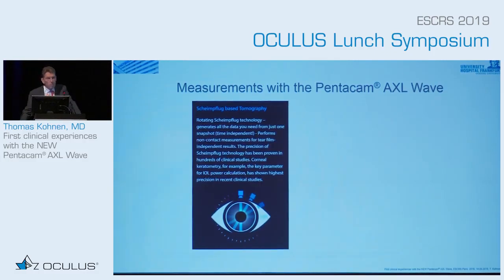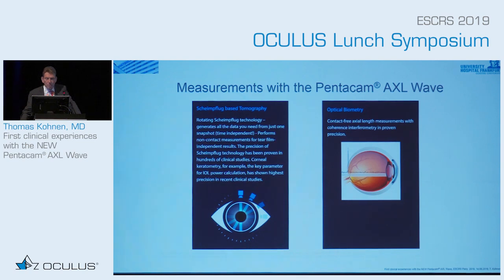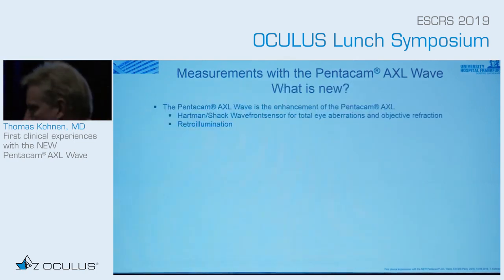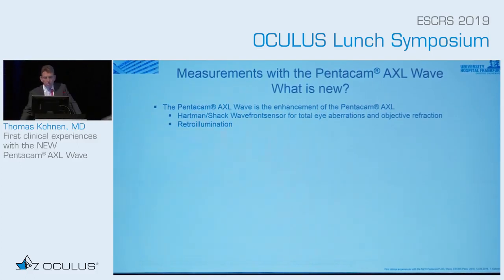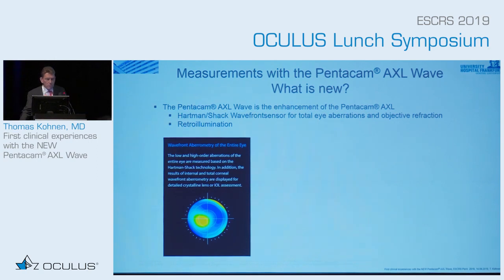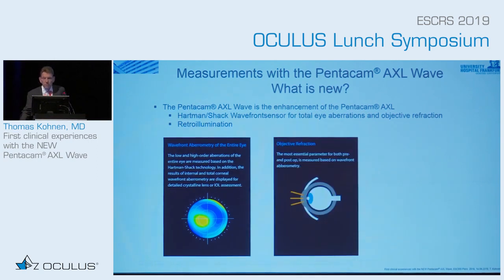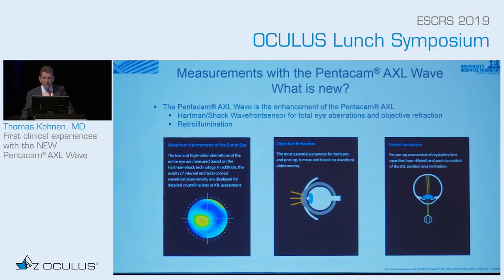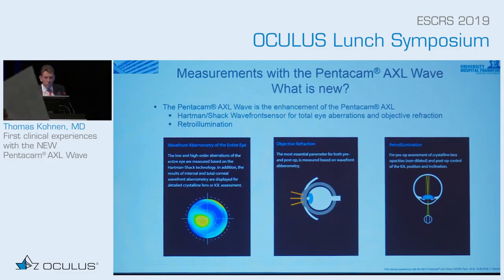Scheimpflug tomography and optical biometry — that's not new. But what is new is that the Pentacam AXL Wave is an enhancement of the previous iteration, because it also takes Hartmann-Shack wavefront sensor and retroillumination measurements. So you see wavefront, optical refraction, objective refraction, and retroillumination as a new addition to this new device.